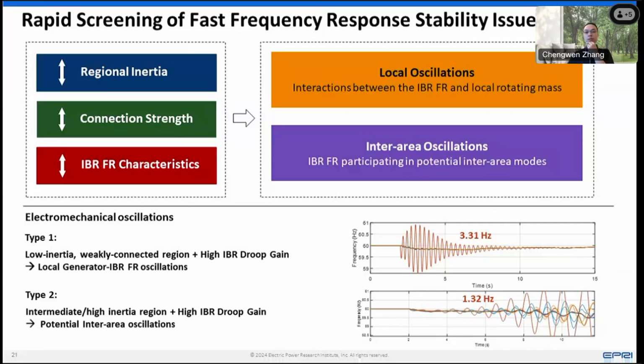The major two types we observe are, one, local oscillations. That's mainly because if you have a very low inertia region with a very high IBR penetration using those IBRs to provide a very strong frequency response, combined with a weak connection to the rest of the system, you can have purely local interactions between those local generators and the IBR.